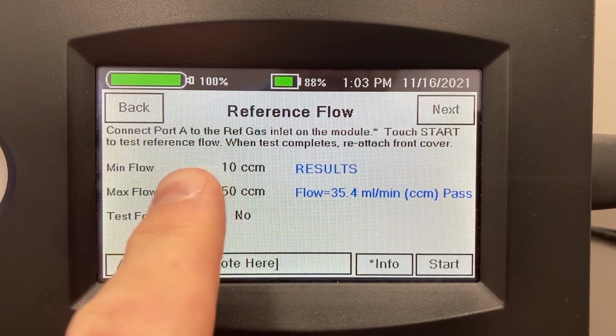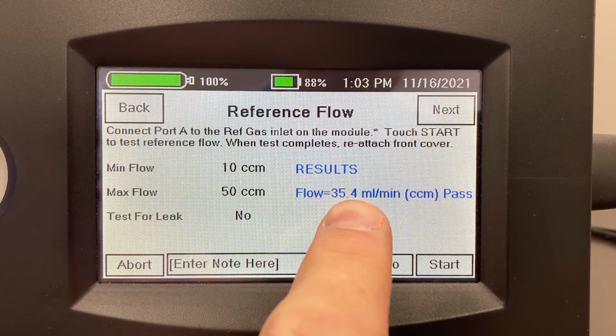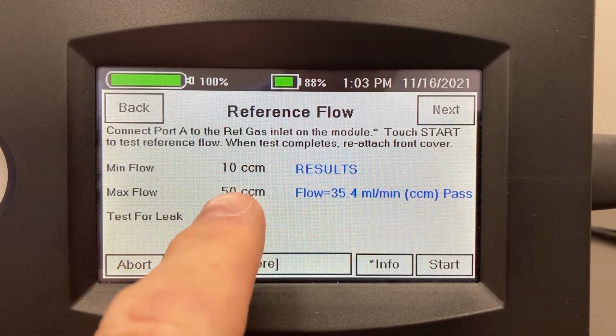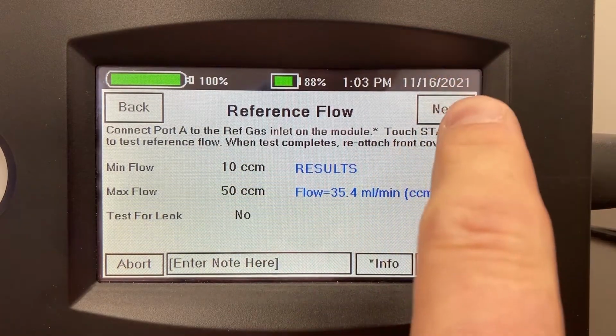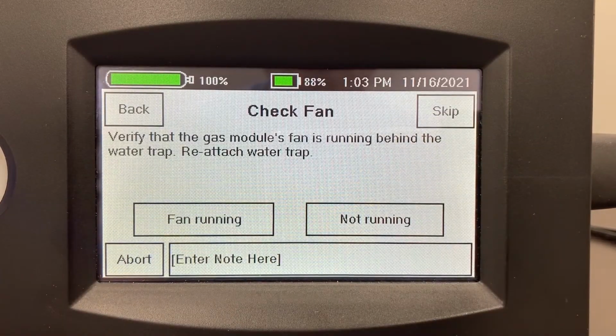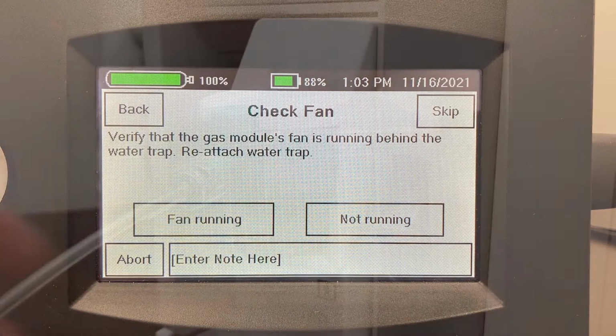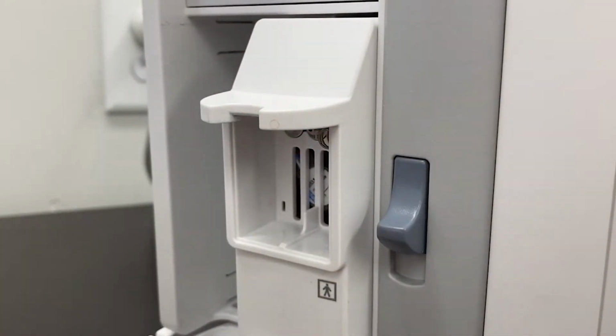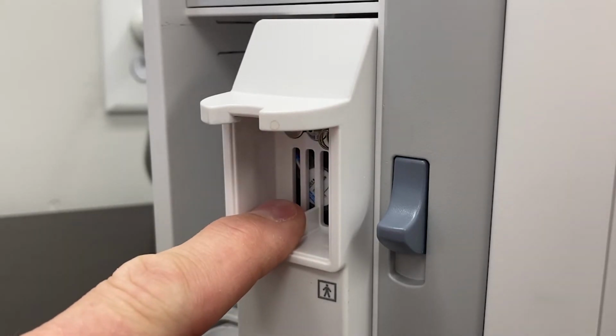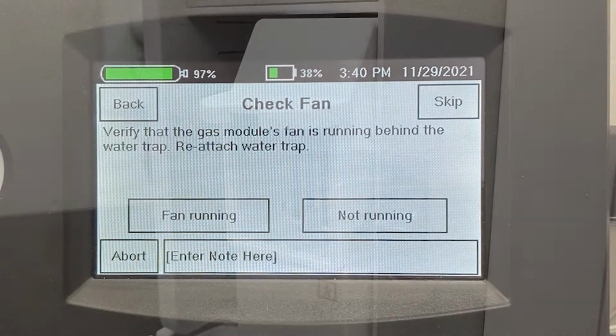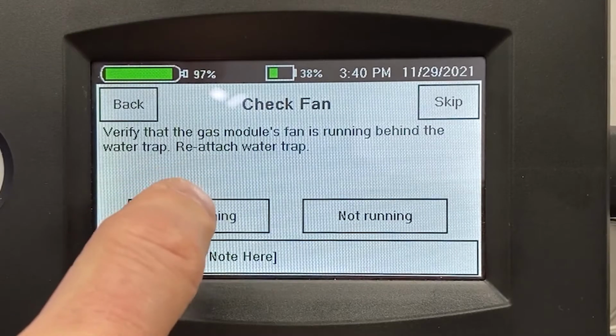So the reference flow rate was 35.4. It had to fall somewhere between 10 and 50. So that's a passing result as well. Next, we're going to check the fan. We do this by removing the water trap and looking or just even listening to the fan, which is right behind the water trap. You can hear it running and then it passes.